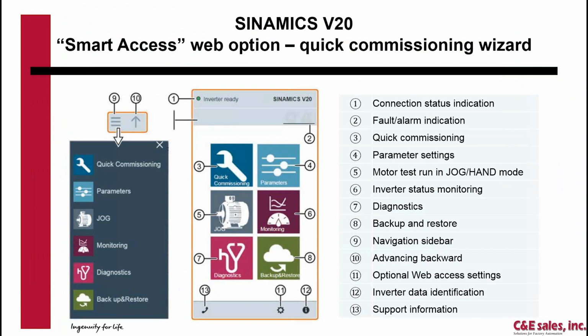Monitoring is going to show you a basic list of parameters that you want to monitor in a normal drive, voltages and currents and speeds and such. Diagnostics is going to highlight if you have drive warnings or errors and what they are, to help do some troubleshooting. Number 8 is backup and restore, so you can back up drive parameters onto the Smart Access module, save them there, and then reuse them later or download to another drive.